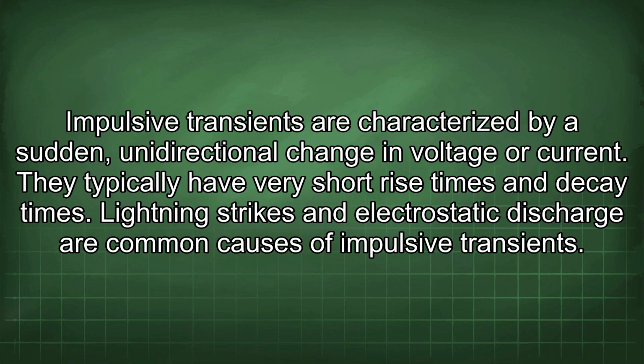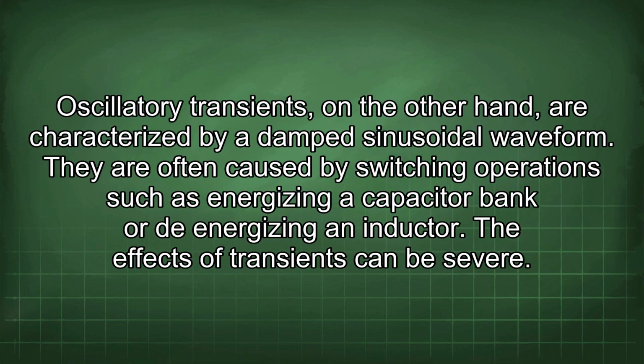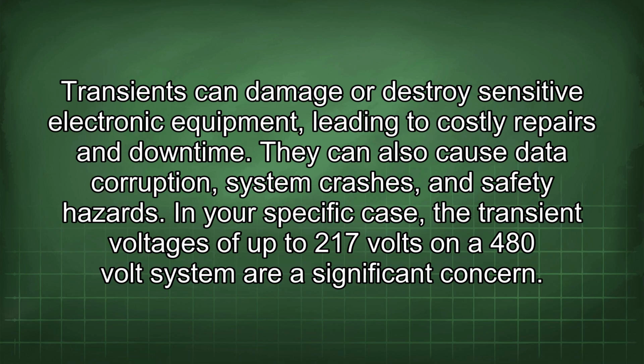Impulsive transients are characterized by a sudden, unidirectional change in voltage or current. They typically have very short rise times and decay times. Lightning strikes and electrostatic discharge are common causes of impulsive transients. Oscillatory transients, on the other hand, are characterized by a damped sinusoidal waveform. They are often caused by switching operations such as energizing a capacitor bank or de-energizing an inductor. The effects of transients can be severe. Transients can damage or destroy sensitive electronic equipment, leading to costly repairs and downtime. They can also cause data corruption, system crashes, and safety hazards.